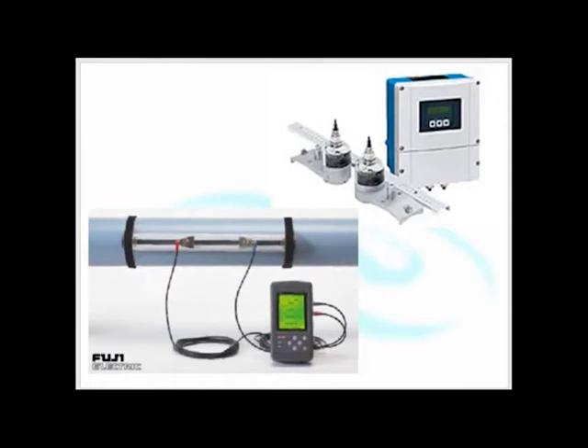I lose accuracy, but generally speaking, the production people don't even notice. It'd be great. I recommend you have one of these little strap-on ultrasonic flow meters in your toolkit. They cost $2,000 or $3,000, but it'll pay for itself in the first call out. So that's the time of flight one. You do need to have something in the fluid to be a carrier. So let's have a little think about this. Will it work with gases?